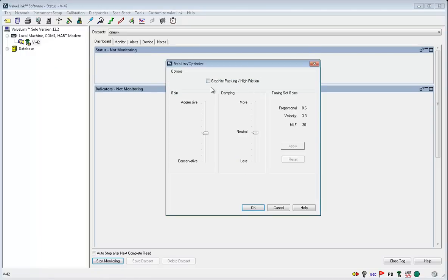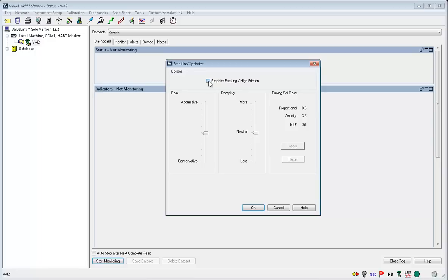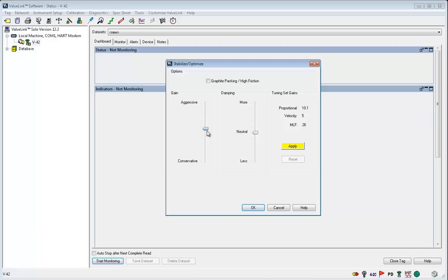If your valve assembly has graphite packing or high friction, check this box. Now we will go through what these sliders do. You can see that changing the gain changes the forward path, velocity feedback, and the minor loop feedback. This is used to set the dynamic response of the valve. Keep stability in mind as you change this.